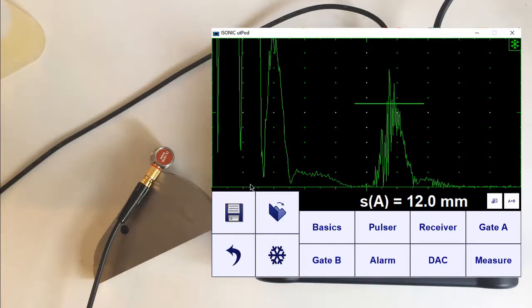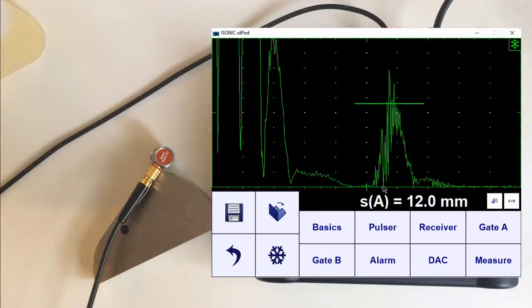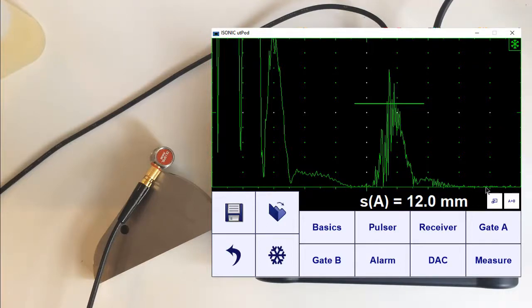Within the A-scan, we see a signal which is the so-called initial pulse — the transmitted pulse from the electronics to the piezoelectric element in the probe — causing signals at the start. After that, the vibration stops and we have a waiting time. After that waiting time, we get this signal coming from the back wall, and then we can measure it. The x-axis is either the time axis, or calibrated as the depth axis — in this case calibrated to give indications in millimeters, so it represents distance.